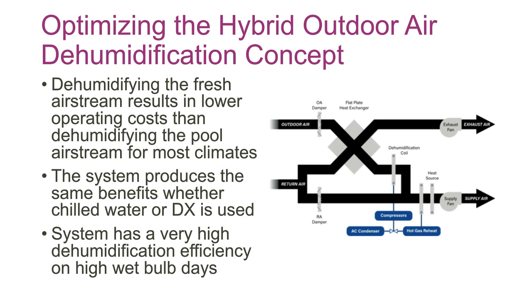So if you'll notice on this diagram, cooling coil is in the outside air after the air-to-air heat exchanger. And what you get is that, let's say for 3 months we need to use the dehumidification, the chilled water or DX. Typically 2 out of those 3 months, and sometimes even more, the outside air has less energy in it than the pool air does. And so even though we're using mechanical dehumidification in those months, we're saving energy by having to use less DX cooling to achieve the concept because the enthalpy of the outside air is lower.